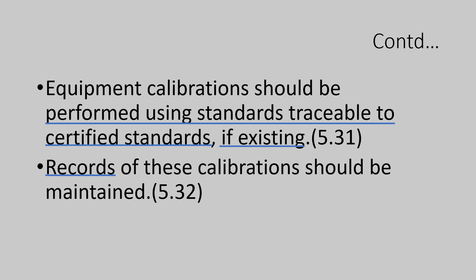Let us see what section 5.32 says: records of these calibrations should be maintained. This means the calibration data is updated immediately after completion of calibration work. Past history of calibrations should also be filed together for easy retrieval of calibration data.